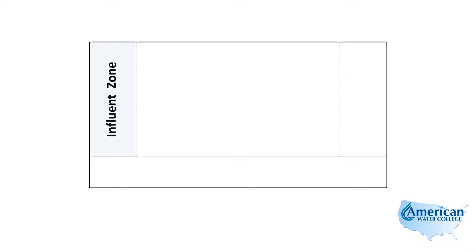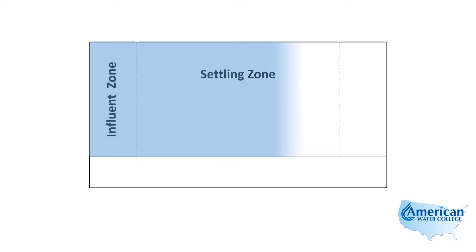Here we have a rectangular sedimentation basin with its influent zone. The first zone of a rectangular sedimentation basin is the influent zone, where water enters the tank. As the water moves through the tank, it enters the settling zone, where settling of particles takes place. At the end of the basin is the effluent zone, where the water leaves the basin.